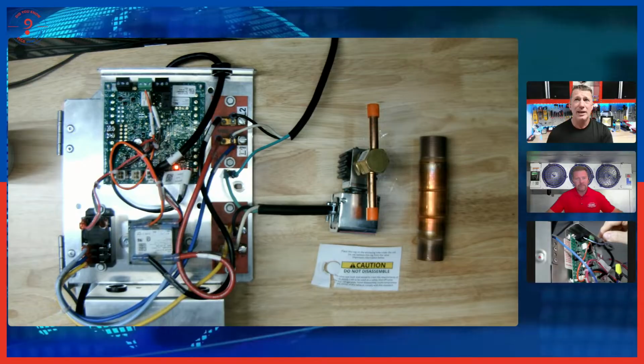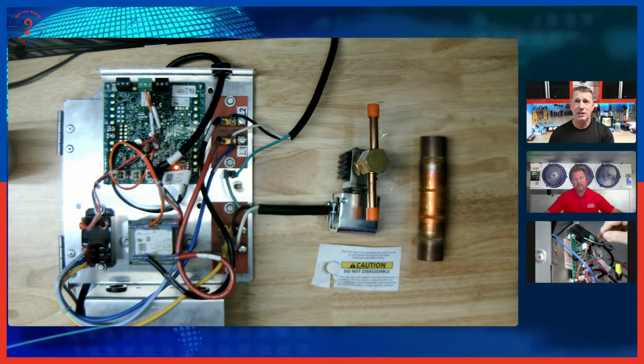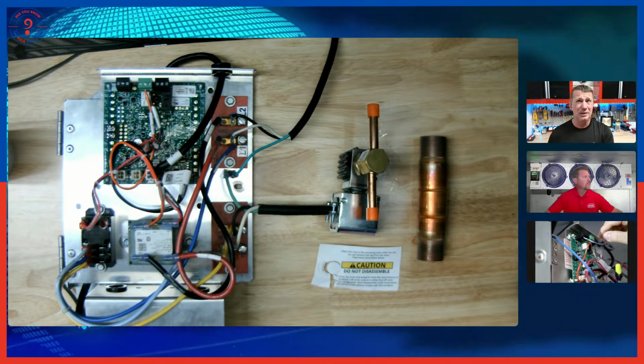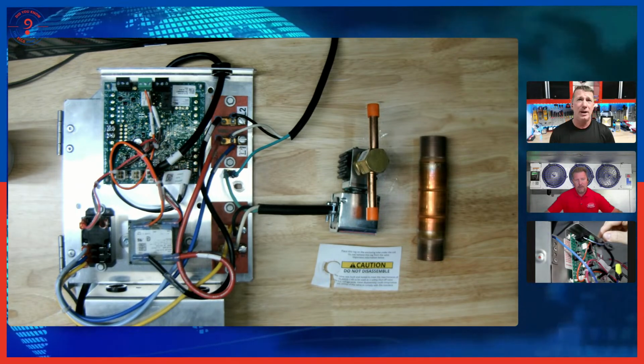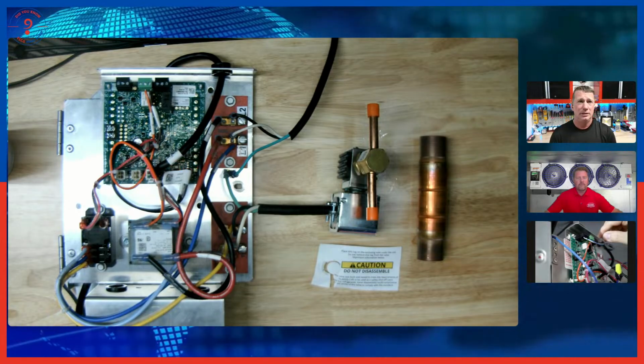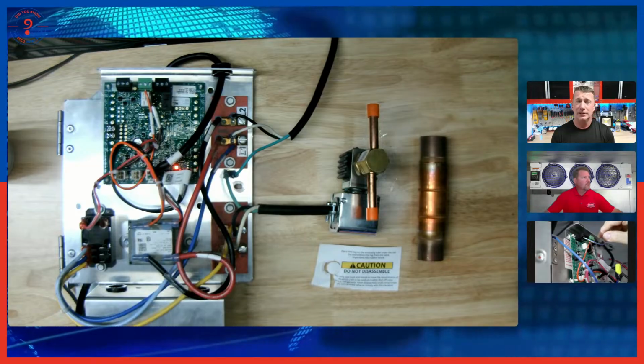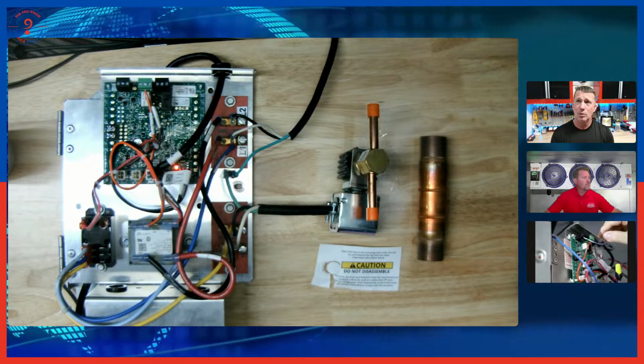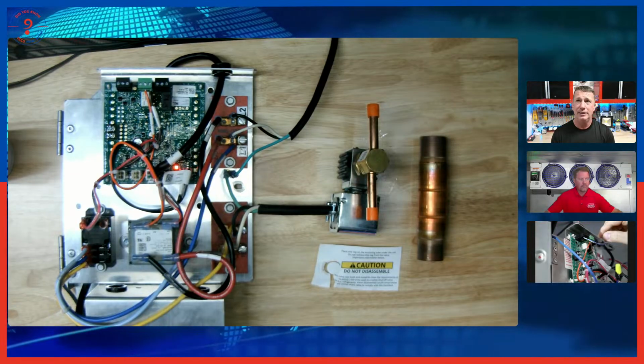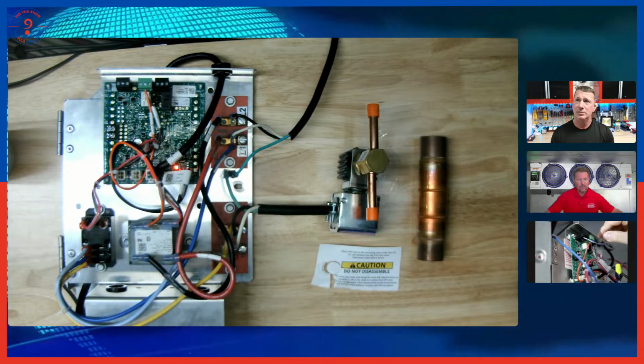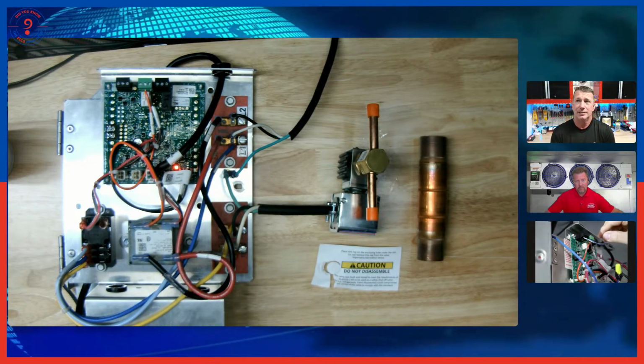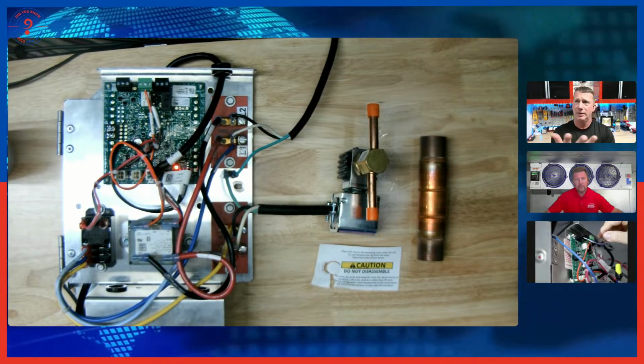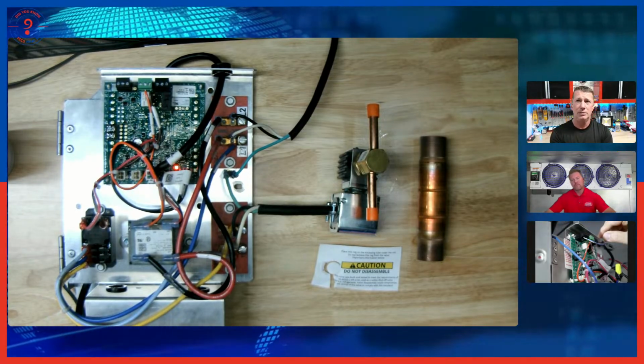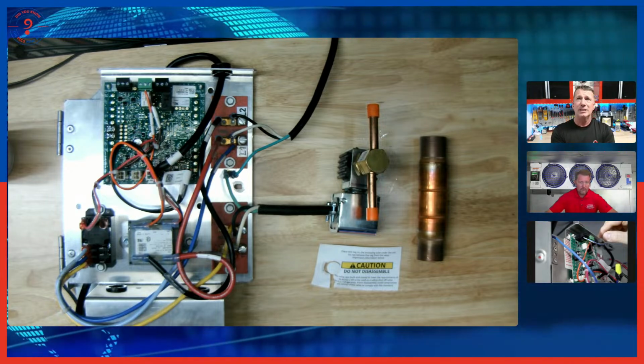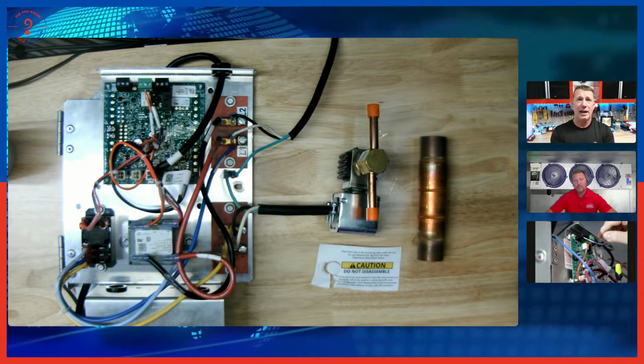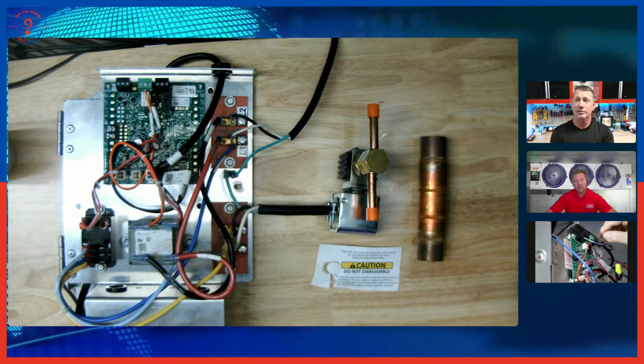Absolutely. So when we look at A2L control and mitigation versus the A1, this is really all we're looking at, right? If we were talking about a residential, light commercial HVAC system, we were talking about a refrigerant leak detection sensor that's connected to a mitigation control board. And if there was a leak event, it's just going to shut off the ignition sources, shut off the outdoor unit, and turn on the fans. Well, if we think about this scenario, say we've got our walk-in freezer, the fans are running most of the time, except for in defrost. What is going to be our sequence of operation if we were to have a leak on an A2L refrigeration system from Heatcraft?